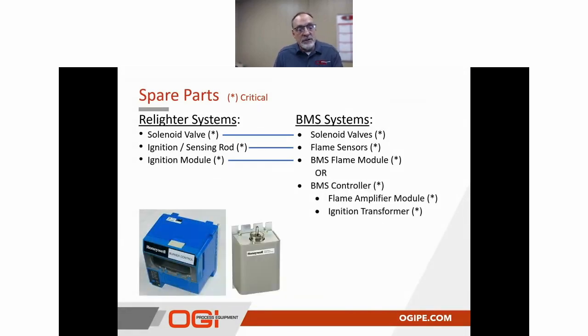The next is obviously, this is where things start to separate a little bit. If you have a more elaborate or complex electronic control system, you might have, like in this case, a Honeywell burner management system. It's important to have that controller on your shelf, as well as the flame amplifier, and as we're showing here, the ignition transformer. Those are the common parts that are potentially going to fail based on any voltage surges, or just in time the ignition transformer gets weak for the work that it has to do to relight the burner when there's a call for heat or whatever there may be.